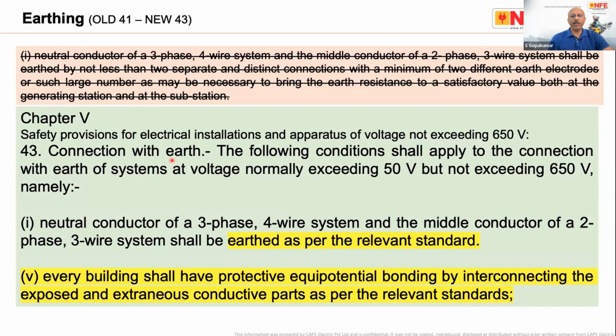If we look at the whole subject, it's part of the safety measure called fault protective measure, called protective equipotential bonding and automatic disconnection of supply. Regulation 43, sub-regulation 5, says very clearly that every building, irrespective of whether it is a house, a hospital, a hotel or an industry, must have this safety measure called protective equipotential bonding. You can read it: every building shall have protective equipotential bonding by interconnecting exposed and extraneous conductive parts. So, as I said, the complete safety measure is protective equipotential bonding and automatic disconnection of supply.